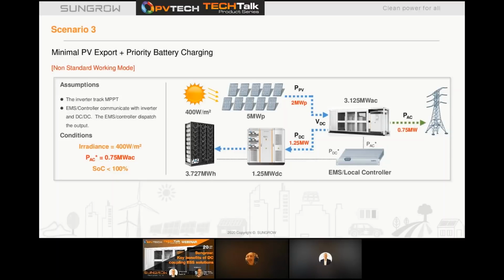Scenario 3 sees the first of the non-standard working modes. So the irradiance in this case is low at 400 watts per meter square, 2 megawatts being produced. State of charge of the battery is low and requires charging. The system prioritizes the recharge of the battery over the export of energy to the grid. In this case, we have 1.25 megawatts going into the battery and just 0.75 megawatts going to export to the grid.